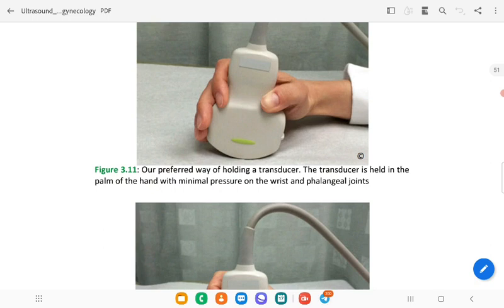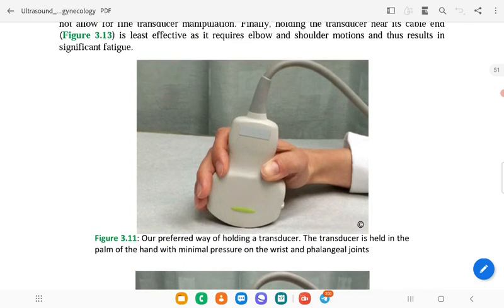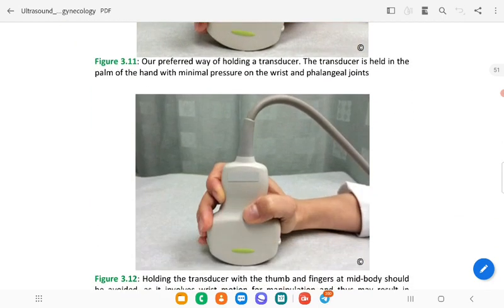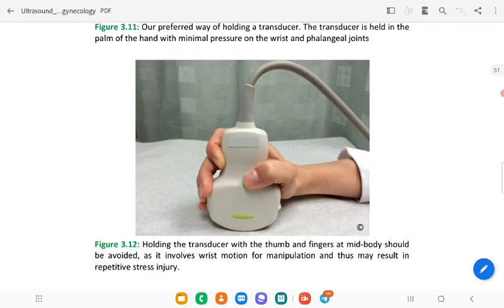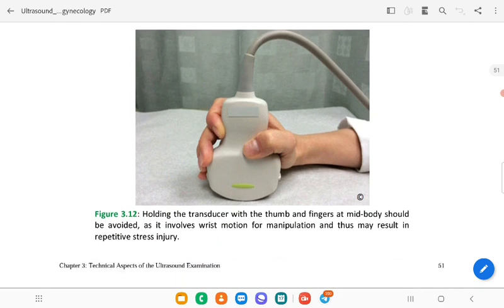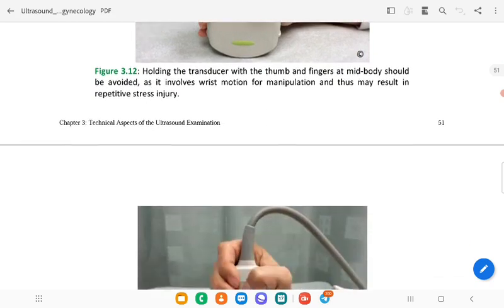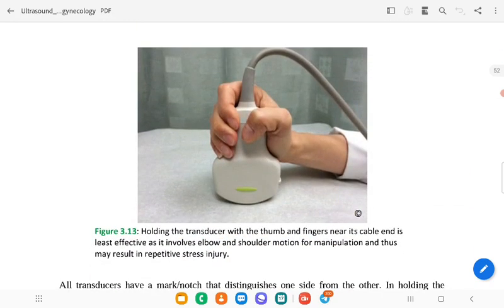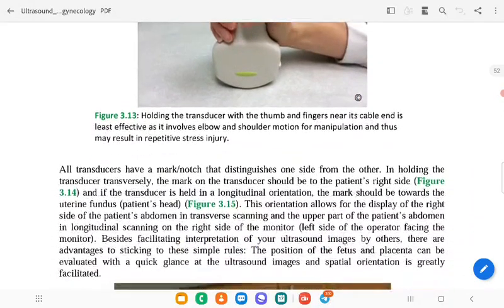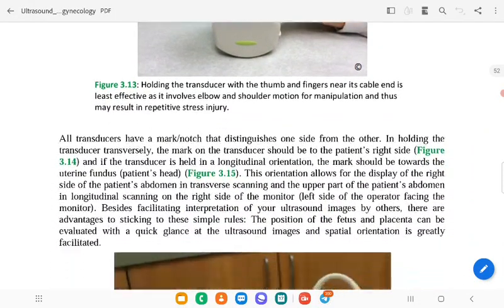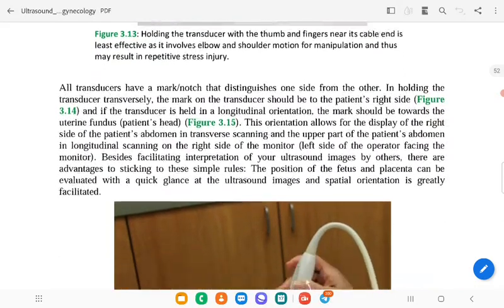Our preferred way of holding the transducer is at the palm of the hand, with minimal pressure on the wrist and phalangeal joints. This is the wrong way of holding the transducer: with the thumb and fingers at mid-body, which should be avoided as it involves wrist motions for manipulation. This may result in repeated stress injury. Holding the transducer with thumb and fingers at its cable end is least effective. It involves elbow and shoulder motion for manipulation. This may result in repeated stress injury.